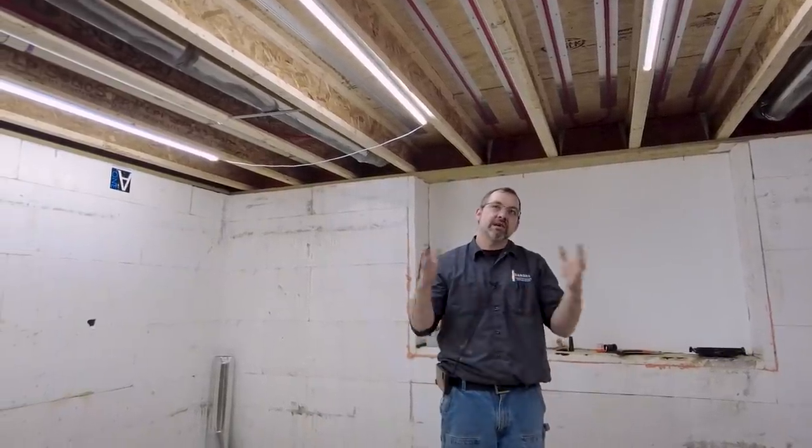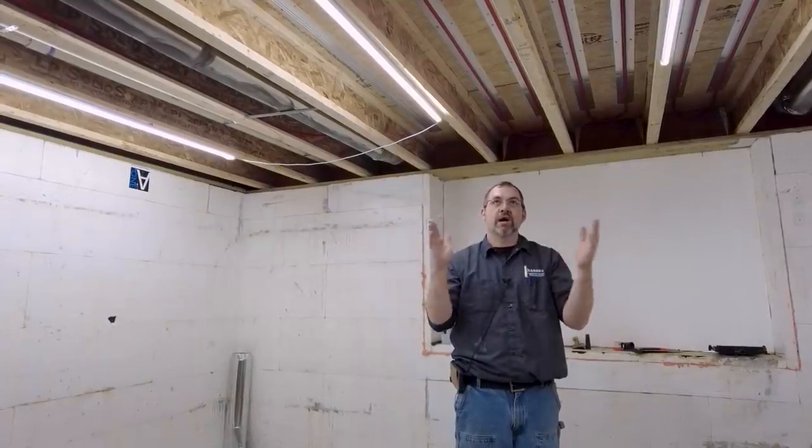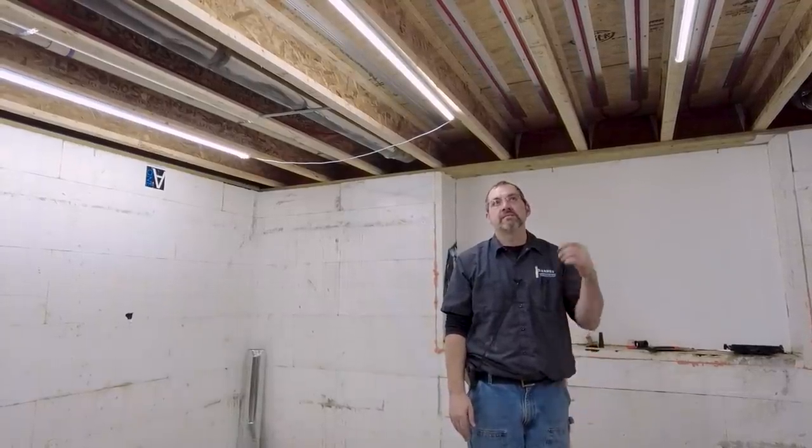There's a couple different sizes, and those usually are wider. These panels are 4-inch wide. I think those are like 6 or 8-inch wide. They're not as thick; these are a very thick aluminum. So the staple-up methods are a little thinner. You just don't get quite the transfer, in my opinion, that you do on these thicker aluminum ones.